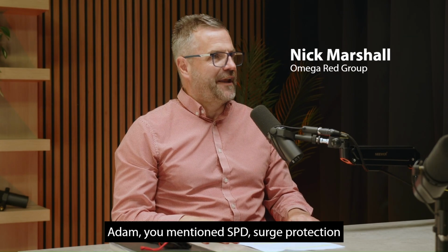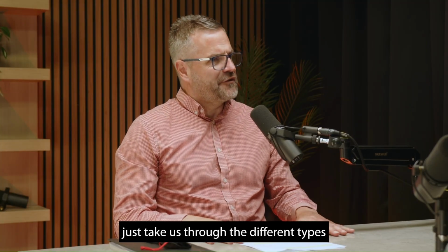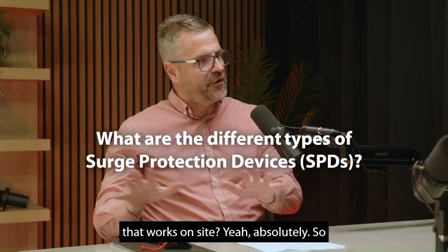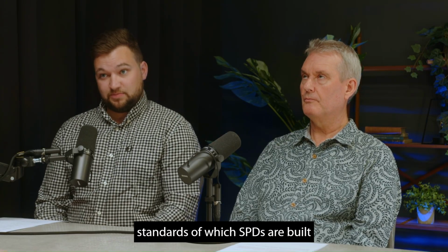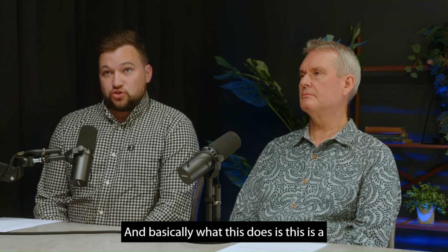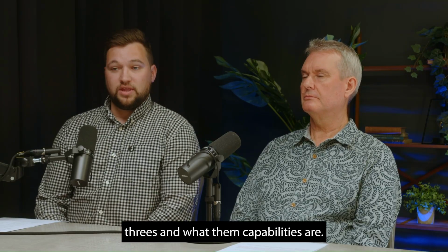Adam, you mentioned SPD, surge protection devices, and we've got different types of levels of protection there. Could you just take us through the different types and why one is used over another and how that works on site? Yeah, absolutely. So it's probably worth mentioning the standards which SPDs are built to. This is BS EN IEC 61643. Basically, this is type testing to make sure that you get your type 1s, your type 2s, type 3s and what their capabilities are.